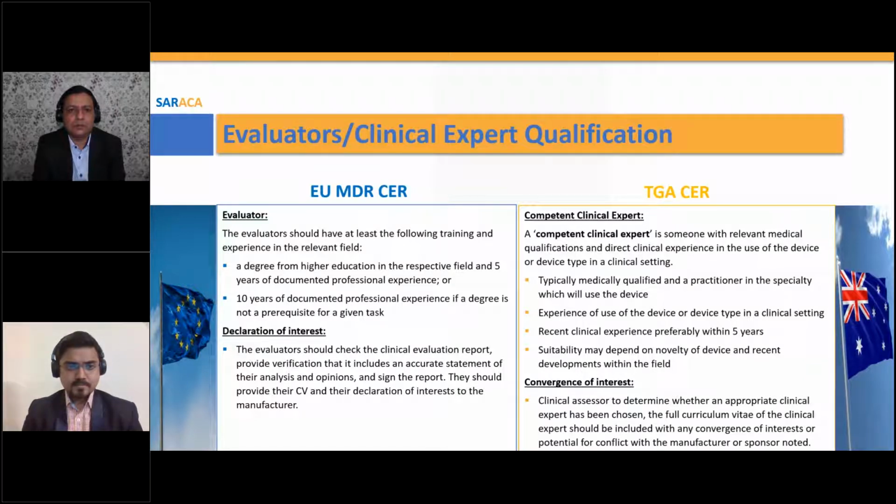On declaration of interest, evaluators should check the clinical evaluation report, provide verification that it includes an accurate statement of their analysis and opinions, and sign the report. They should provide their CV and the declaration of interest to the manufacturer. That is, if they have a direct interest in the sale of the device, if they own a portion of the company, or they buy the device.